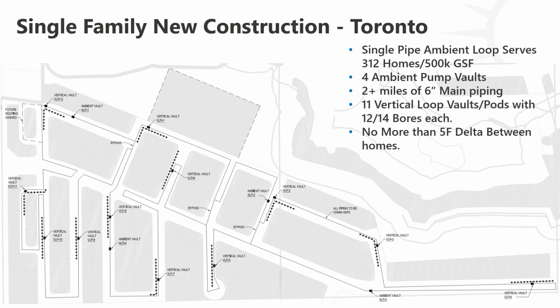Then you just manage the temperature between each resource, and that way you can really slow the flow down. The resource matters, what's its temperature, whether it's sewage heat recovery versus geo in multiple locations, and adding that in keeps your temperatures higher. The warmer or more consistent you can keep the temperature, between 50 and 60, the lower the flow you can run.